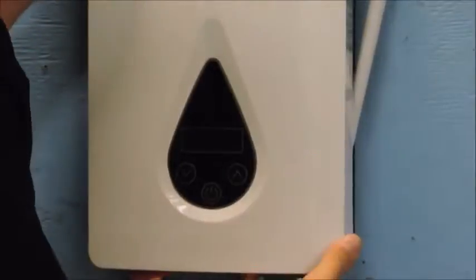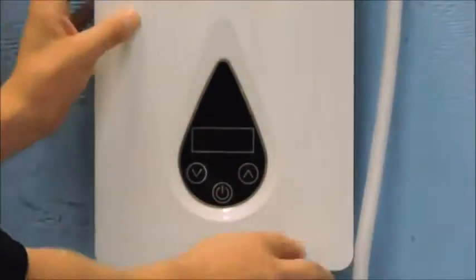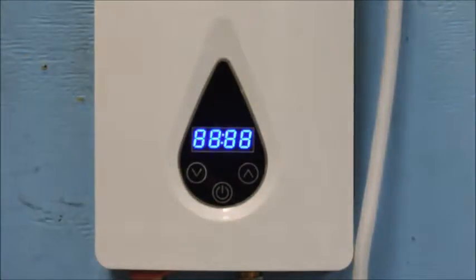Hang the unit back on the wall and replace the front cover before resupplying the power to the unit. At this time, the unit should read the incoming water temperature. If it still displays E3, then replace the inlet temp sensor and make sure that both the connections at the power board are secure.